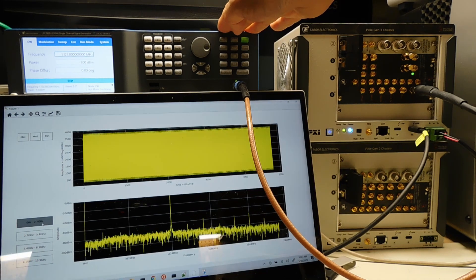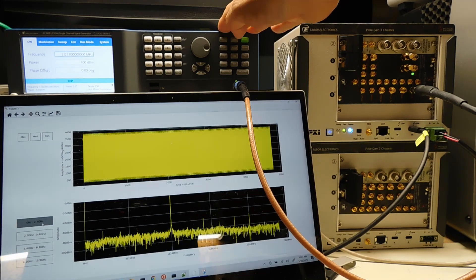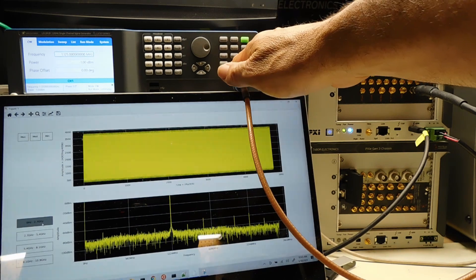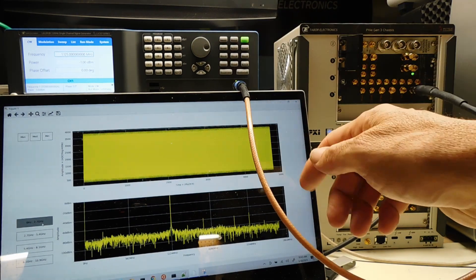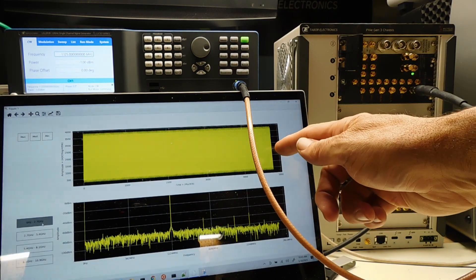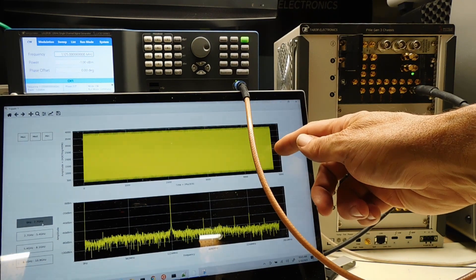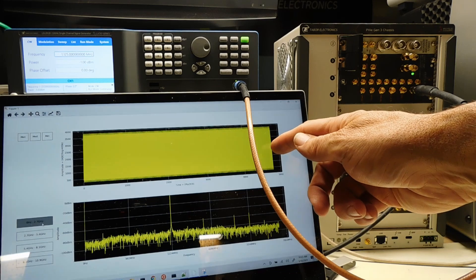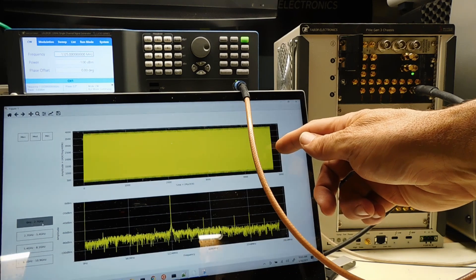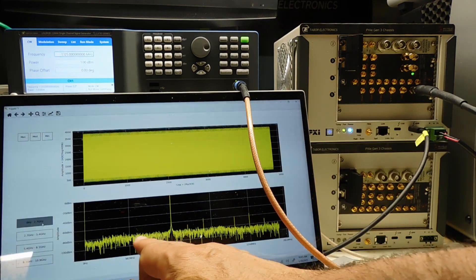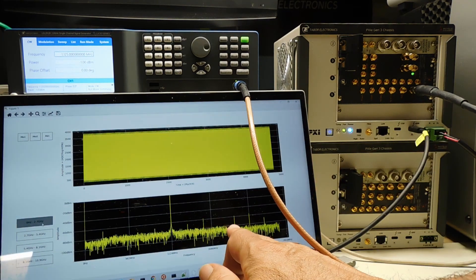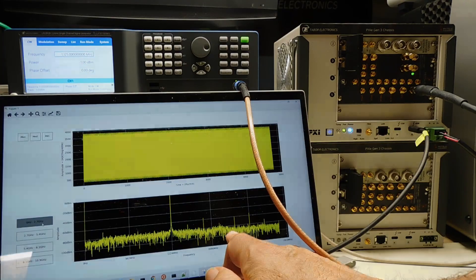1.125 gigahertz at about 0 dBm feeding the digitizer. On the display here, you can see we have the time domain waveform, and you can also see that we have the frequency domain waveform down here.